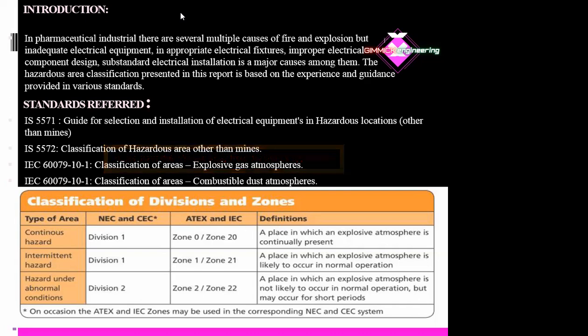Coming to Zone 2, it is likely lower than Zone 1, where fumes are present only during the operation, but not for a long time. For example, during maintenance activity, whenever we are removing any flange, equipment, top dish, or other part, fumes are present for a specific time - that is Zone 2.